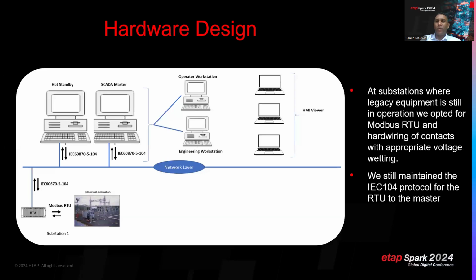The substations where we have legacy equipment still in operation and IEC 61850 protocol was not able to be used, we used the Modbus protocol. And where no comms was available, hardwiring of contacts with appropriate voltage wetting was used to bring in those signals. We still managed to maintain the RTU to master using the IEC 104 protocol.